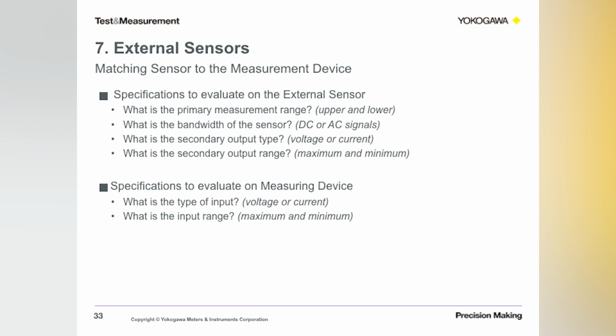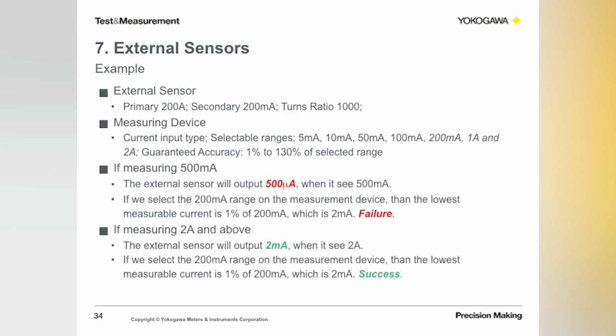True power analyzers will accept current input. So you want to match that to your measurement device and see what input it accepts. Then there's the secondary output range, to make sure that both the minimum and the maximum output signal from your external sensor can be measured by your measurement device. This is an important one, and many engineers either miss or miscalculate this specification. Let's walk through an example that can explain that a little better. Say you're using a 200 amp external sensor that has a 200 milliamp output. On the power analyzer side, you may have a wide selection of ranges, but since your output is 200 milliamps, based on all the ranges that I've shown here, you will most likely select the 200 milliamp range, right?